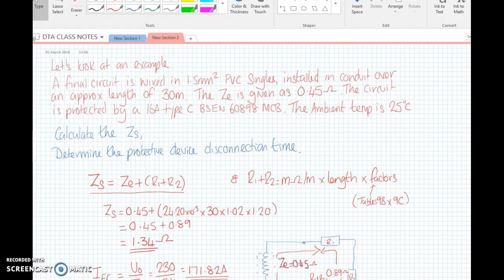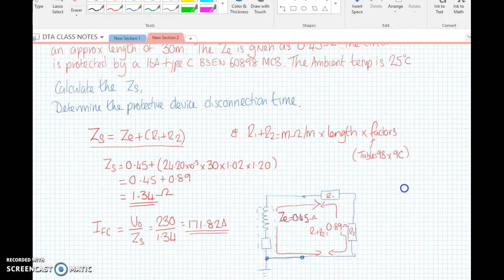Let's look at an example. We've got a final circuit wired in 1.5mm PVC singles in conduit, approximate length 30 meters. The external impedance is 0.45 ohms. The circuit is protected by a 16 amp type C BS EN 60898 circuit breaker, and the ambient temperature is 25 degrees C. We're going to calculate the impedance and determine the protective device disconnection time.